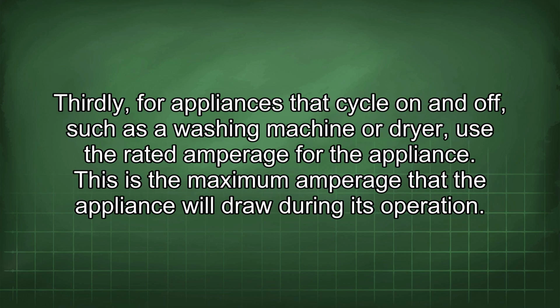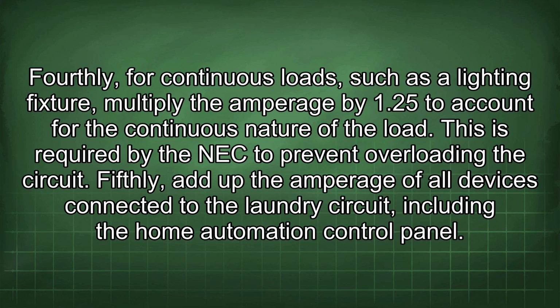amperage. Thirdly, for appliances that cycle on and off, such as a washing machine or dryer, use the rated amperage for the appliance. This is the maximum amperage that the appliance will draw during its operation. Fourthly, for continuous loads, such as a lighting fixture, multiply the amperage by 1.25 to account for the continuous nature of the load. This is required by the NEC to prevent overloading the circuit.